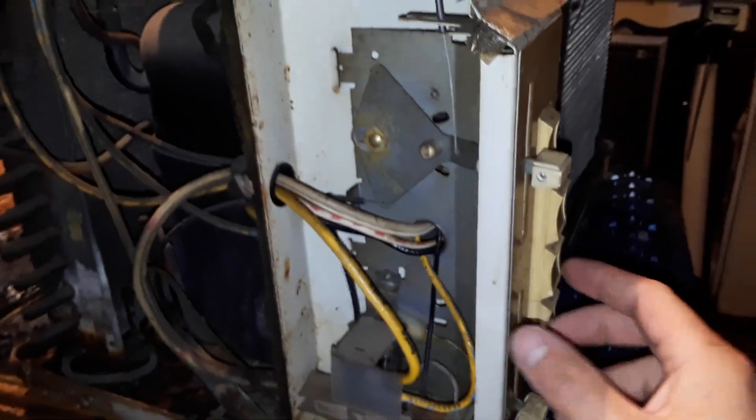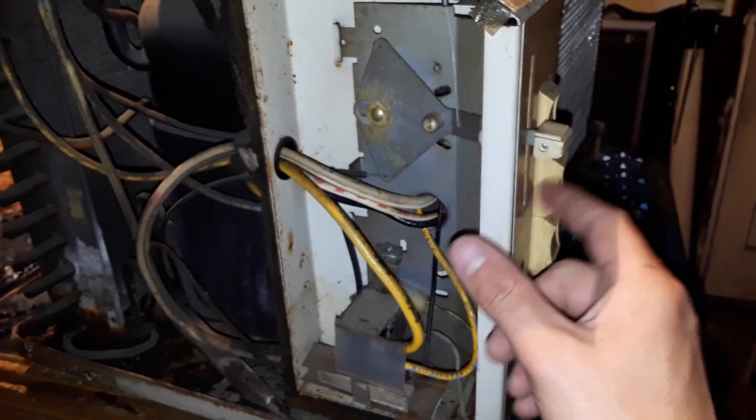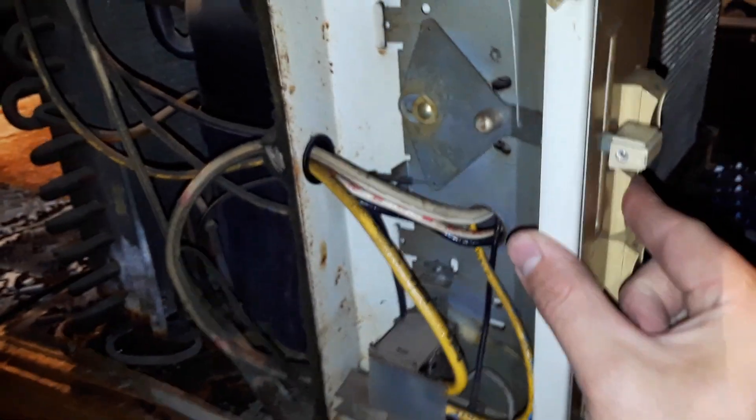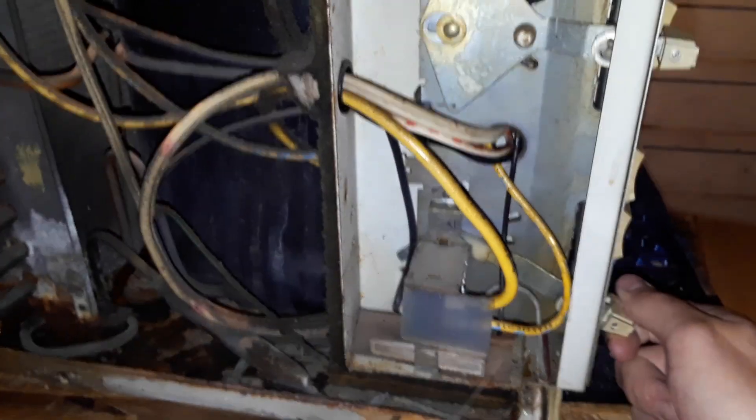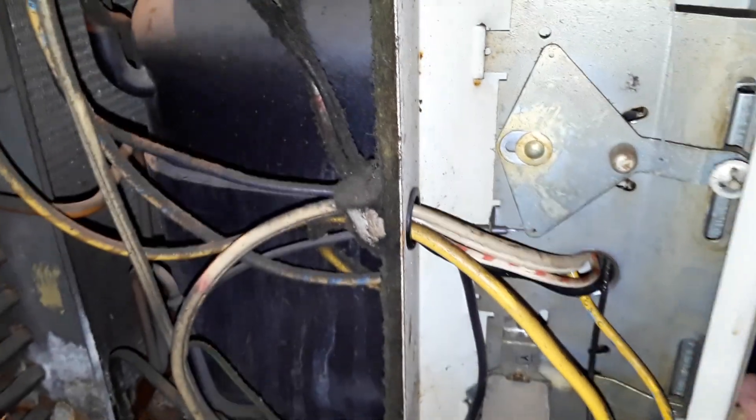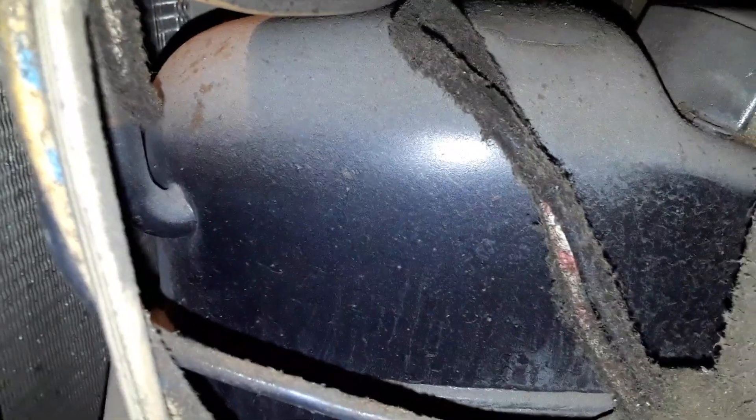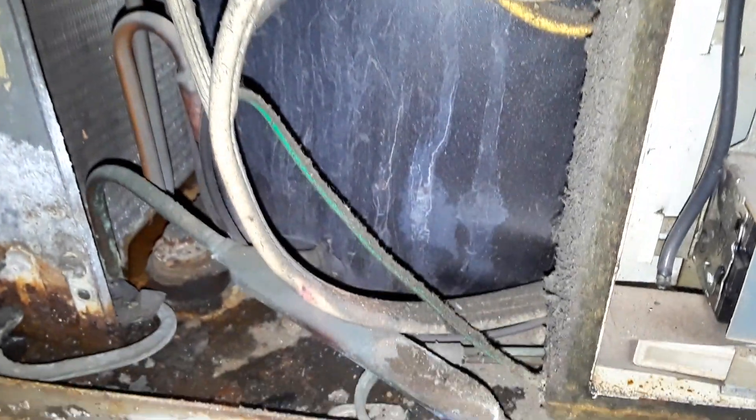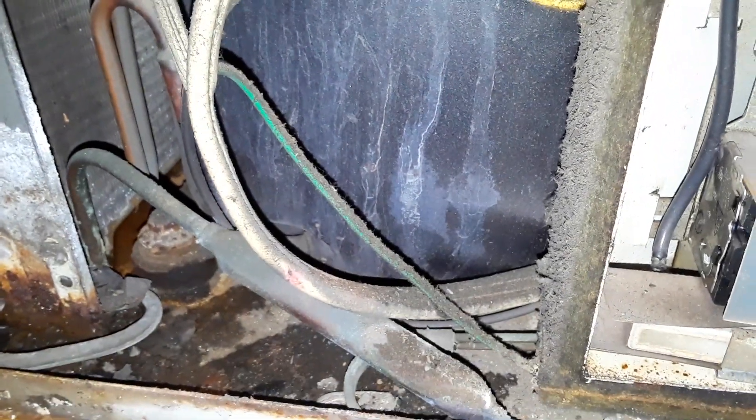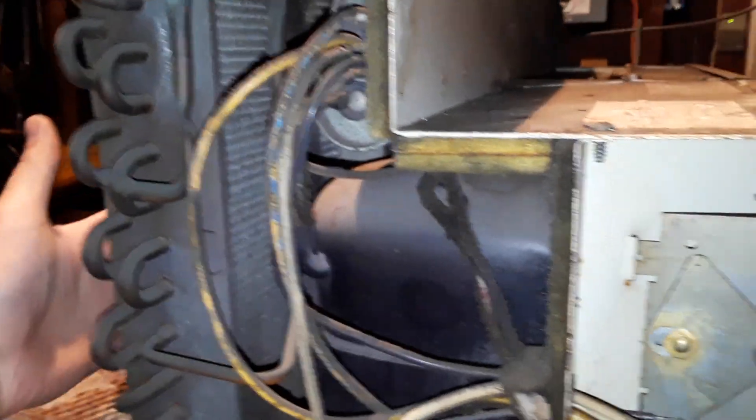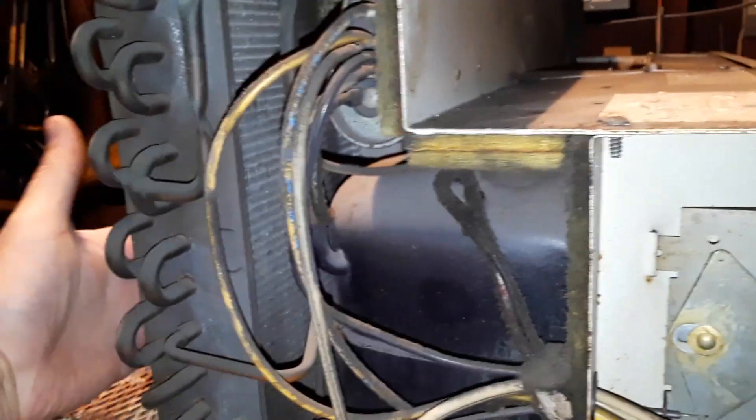The fan's on high. Let's hear the compressor start up - a little bit of a low cool. We're going to shift it on up. It's got head pressure already, that's blowing hot air out of here. I don't want to let it run too long like that because it's not cycling - it's not cooling down the condenser properly with this open. The case is solid on both sides.